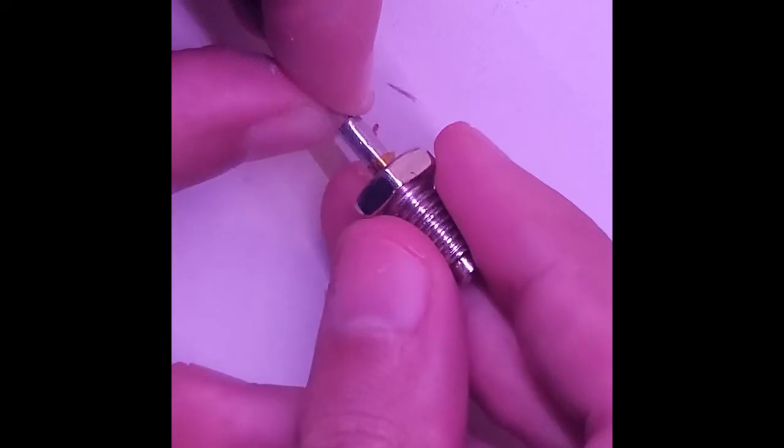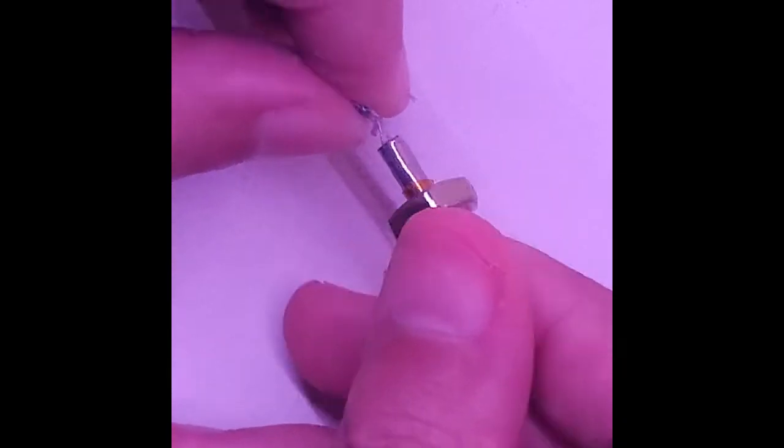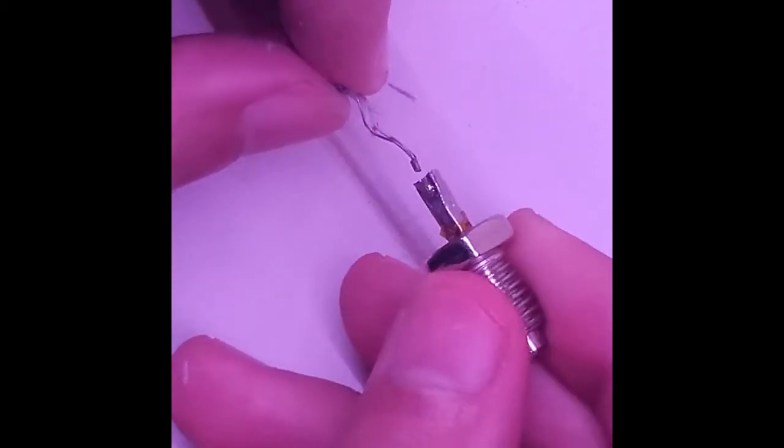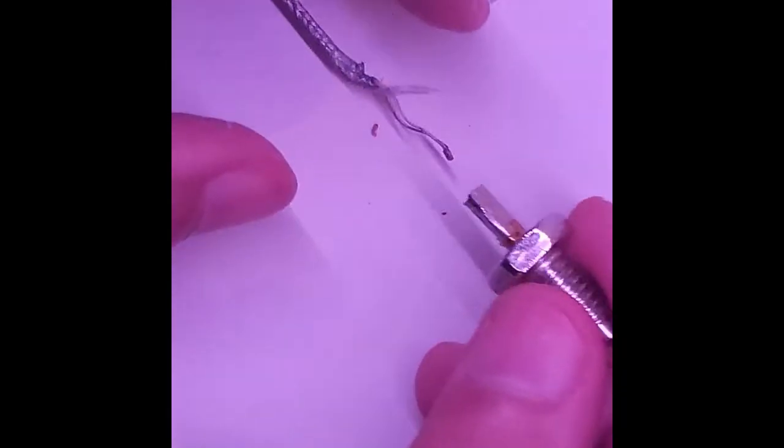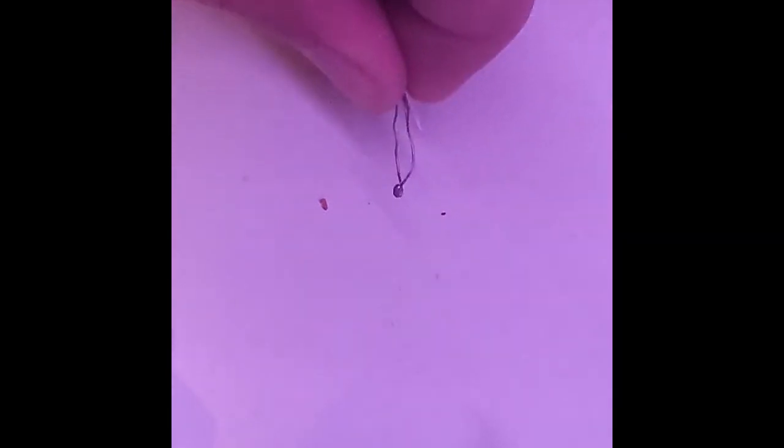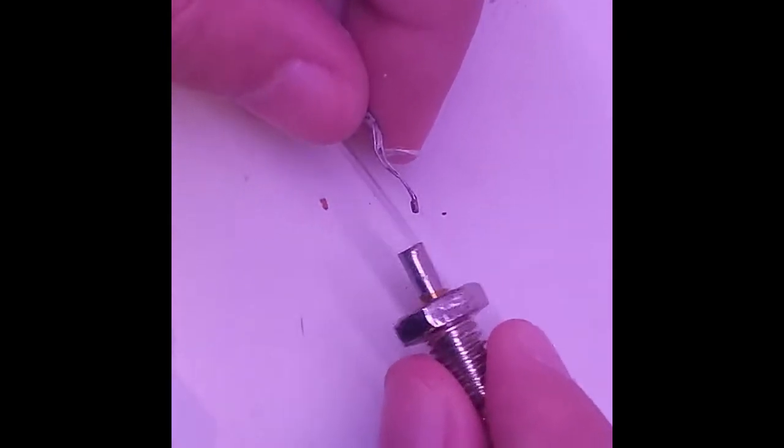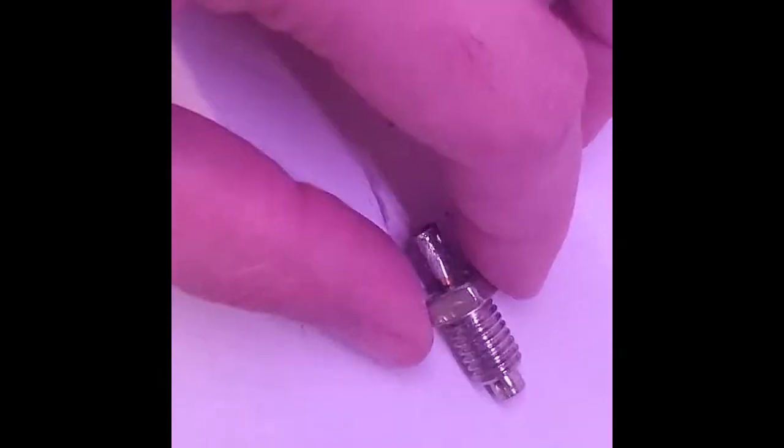The way to fix this to get an accurate temperature reading is: one, you can just remove this thermocouple, but then it's harder to secure it in place. So you might want to put it in here to have a good place to secure it. If you still want to keep this threaded thing, which you have to do to get an accurate reading—and this is important, I've never seen anyone talk about this—what you need to do is take some thermal paste and just put it in here.